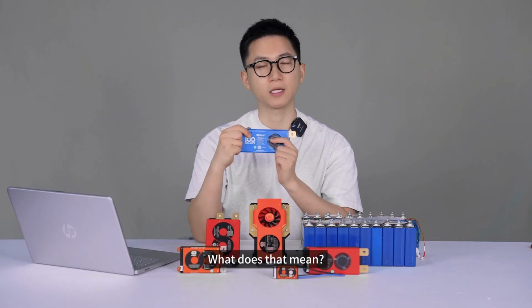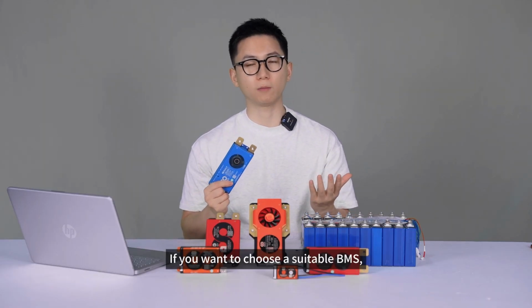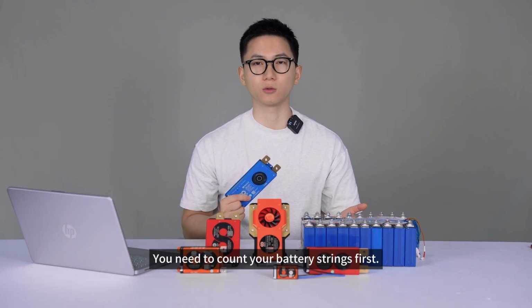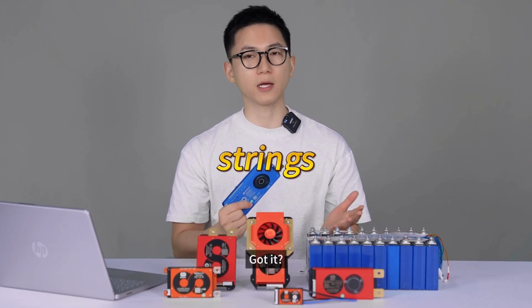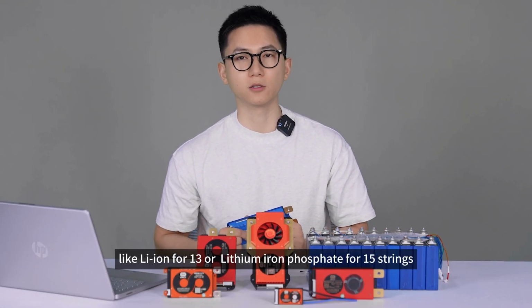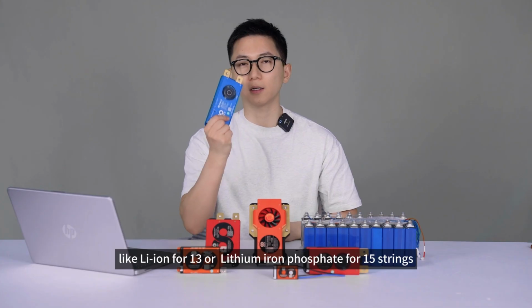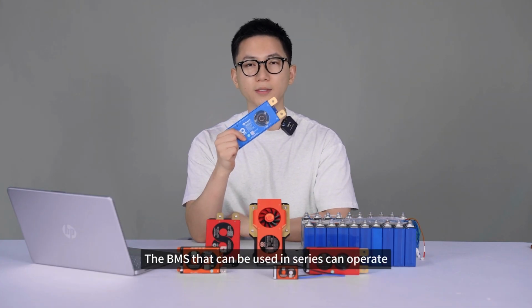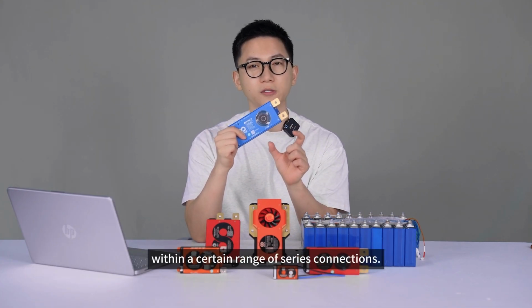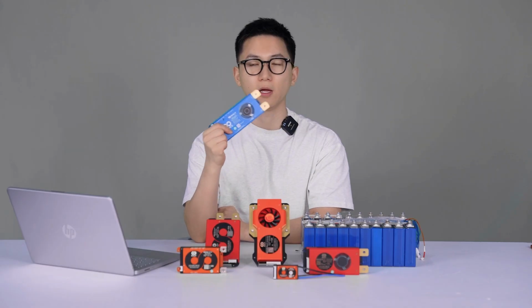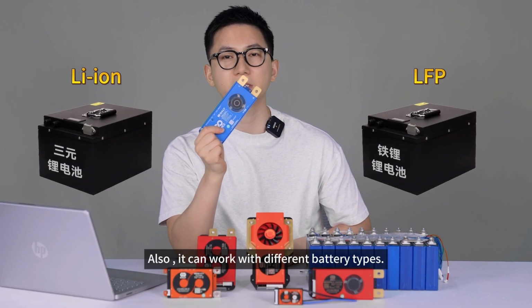What does that mean? As we shared earlier, if you want to choose a suitable BMS, you need to count your battery strings first. Like Li-ion for 13 strings or lithium iron phosphate for 15 strings. The BMS that can be used in series can operate within a certain range of series connections, so it can fit that. Also, it can work with different battery types.